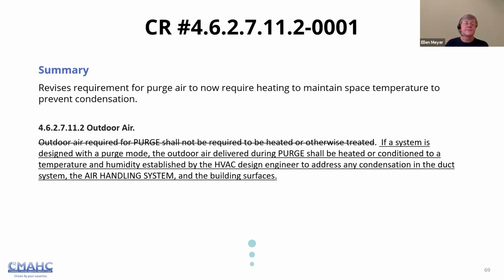It was originally written differently. The rewording was to give it a little bit more leeway. So you don't necessarily need to condition it to the point where it's exactly like your indoor air, but that's up then to the design professionals to figure out, okay, what do you need to do to prevent condensation on these surfaces when you are pulling in air from the outside. So there is a significant change. So make sure that you read the original change request with the text in there, and then read the new version that's in the TRC review form.